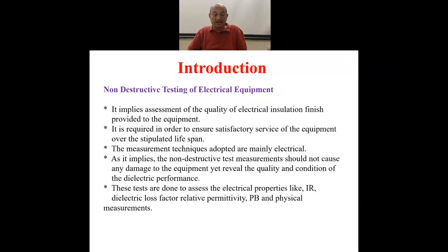For the stipulated performance, another technique has come up, and that is called condition monitoring of the insulation. Rather, people say condition monitoring of the equipment. That means when the equipment is giving you service, the condition of its insulation can be monitored continuously. If something wrong begins, condition monitoring techniques reveal that something is going wrong, and if possible, some measure should be taken or a shutdown should be taken to ensure no fault occurs because of the failure of insulation.